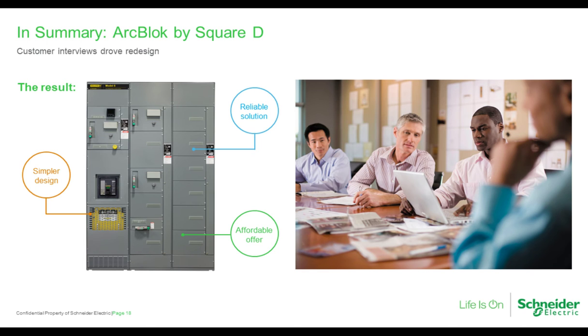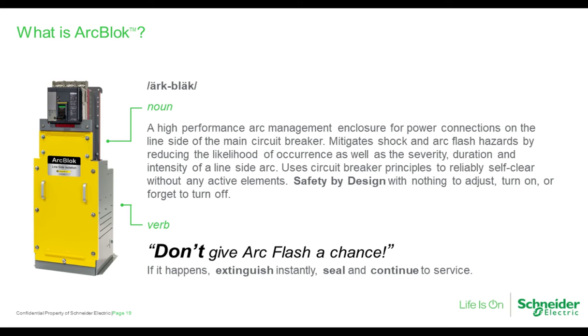Tim explained the technology in detail, right? But what about at system level? What does ArcBlok do? ArcBlok line side isolation technology is a passive system, right? Many available solutions focus on actively removing the arcing fault after it begins on the load side. On the other hand, ArcBlok technology reduces the likelihood of an arc flash incident on the line side, which is usually the worst case scenario from the arc flash calculations due to the upstream protective device.